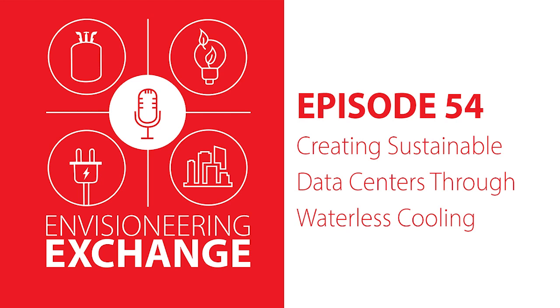That was some of what went into the design. To give you some data points: a traditional, very good data center operating in an immediate hot climate, like Atlanta, which gets pretty hot for a lot of the year, runs about a 9% cooling overhead annually using no water. That benchmarks well, that's probably what you'd expect from a very good adiabatic, evaporative cooling system. So to be at that efficiency level with no water, we feel very good about it.